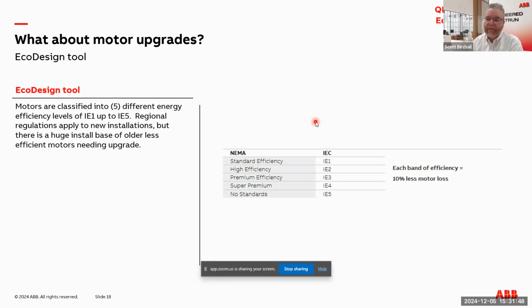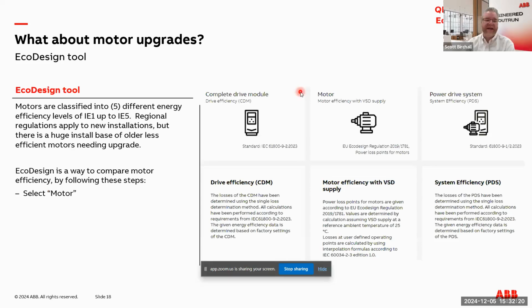Every time you bump up a band in the IE rating, you reduce the losses in your motor by 10% as far as your watt loss. Basically, the heat being produced gets reduced by 10%. So one of the things you need to look at is, say, I've got this pump that's 25 years old. This has been a great motor. I changed out the bearings once, and this motor just keeps on running. I don't need to worry about it. Well, maybe you want to consider replacing that motor with one that's more modern and energy efficient. That's what this next tool is going to do.